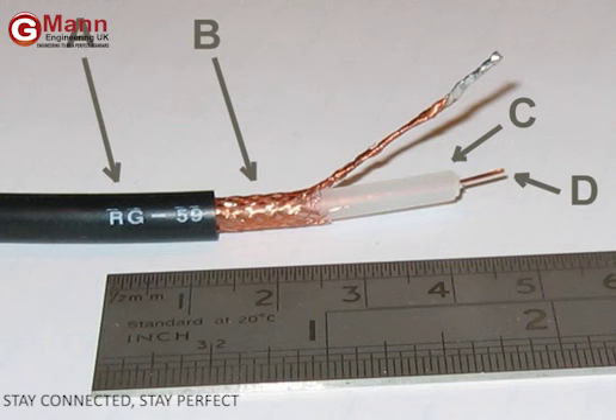Foil shielding is ordinarily accompanied by a tinned copper or aluminum braid shield, with anywhere from 60 to 95% coverage. The braid is important to shield effectiveness because 1, it is more effective than foil at preventing low-frequency interference, 2, it provides higher conductivity to ground than foil, and 3, it makes attaching a connector easier and more reliable. Quad shield cable, using two low-coverage aluminum braid shields and two layers of foil, is often used in situations involving troublesome interference, but is less effective than a single layer of foil and single high-coverage copper braid shield such as is found on broadcast-quality precision video cable.